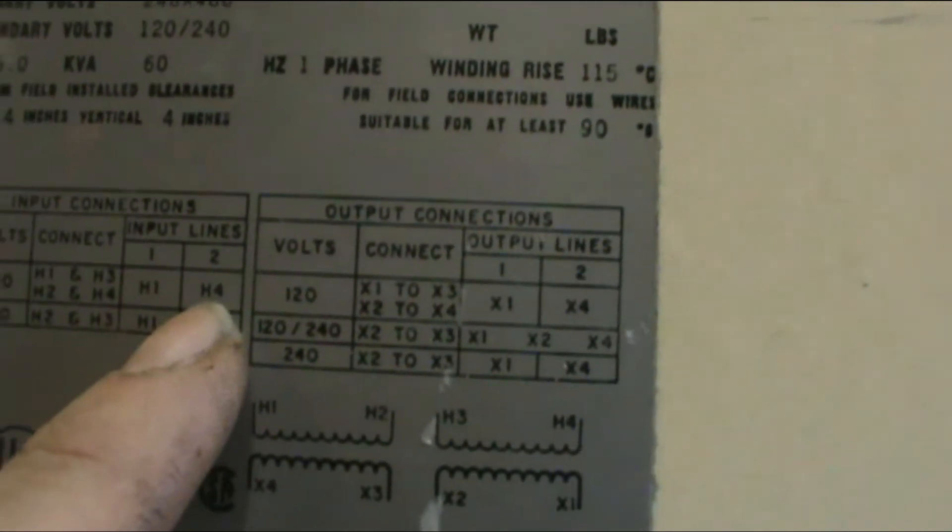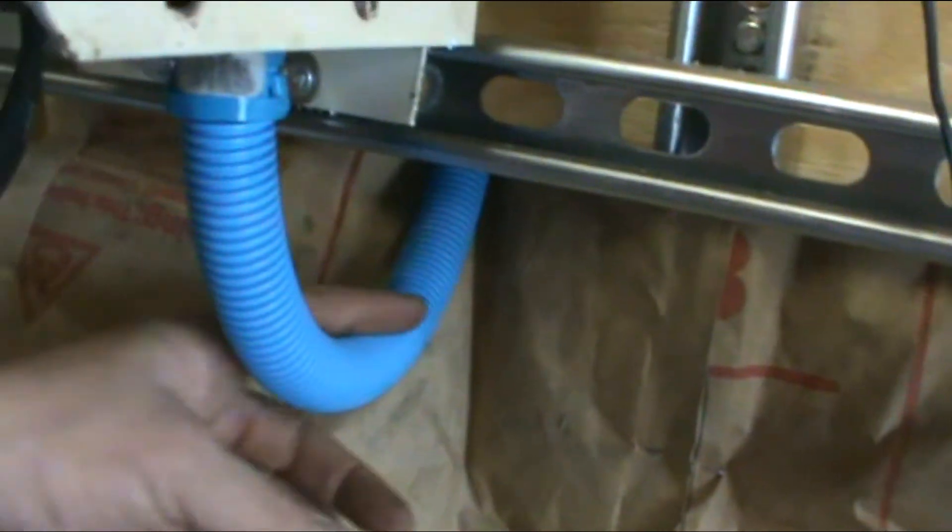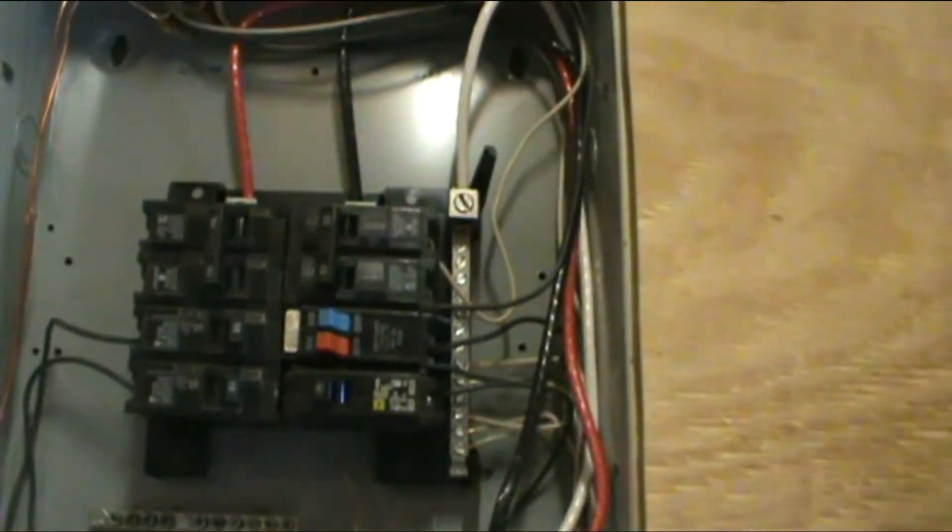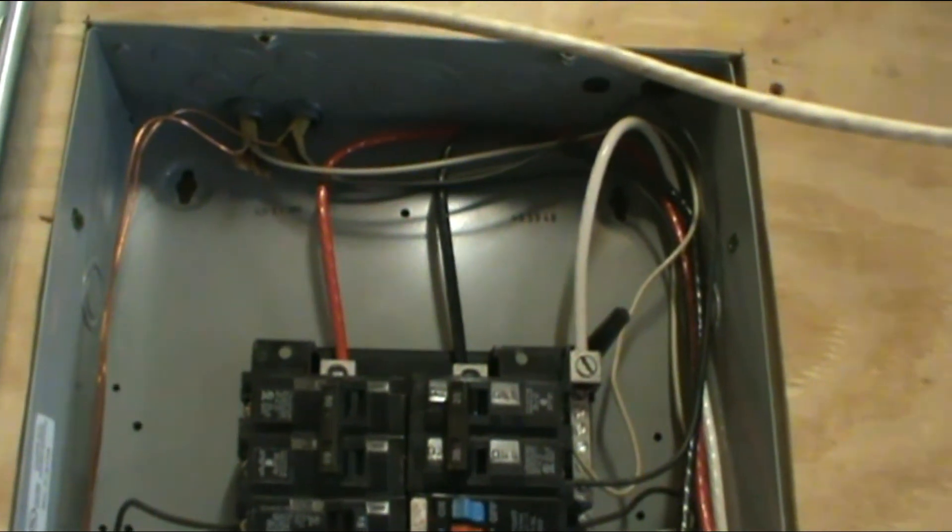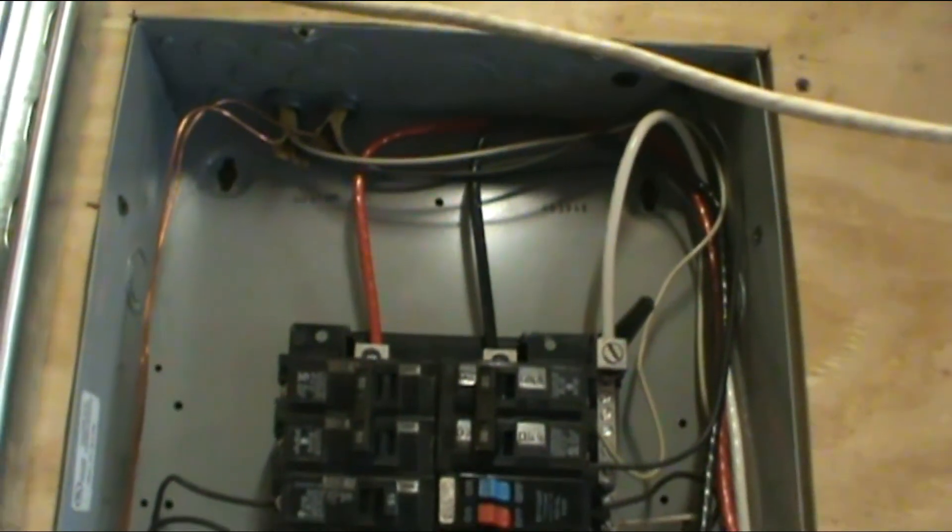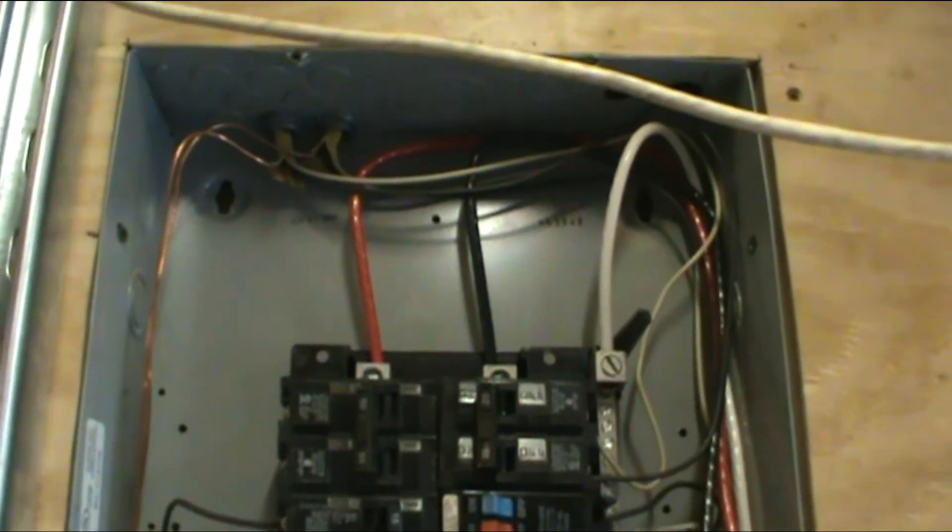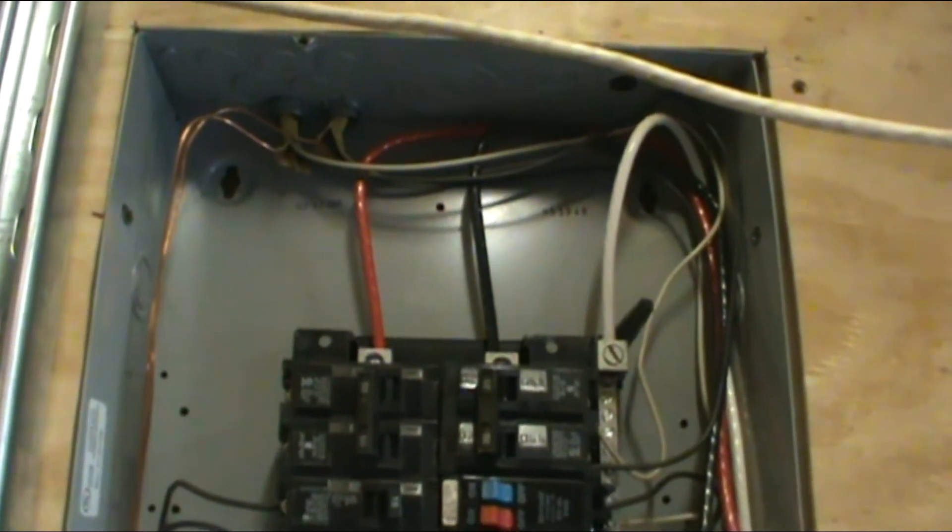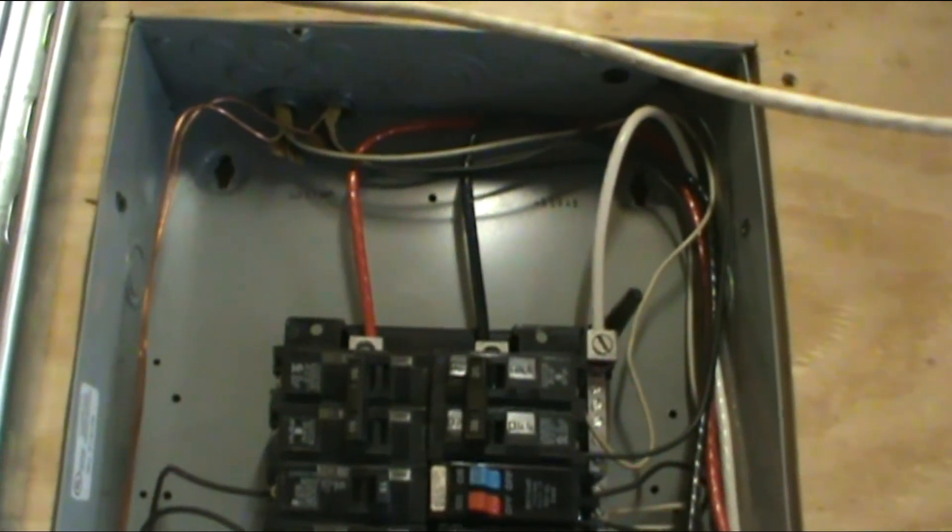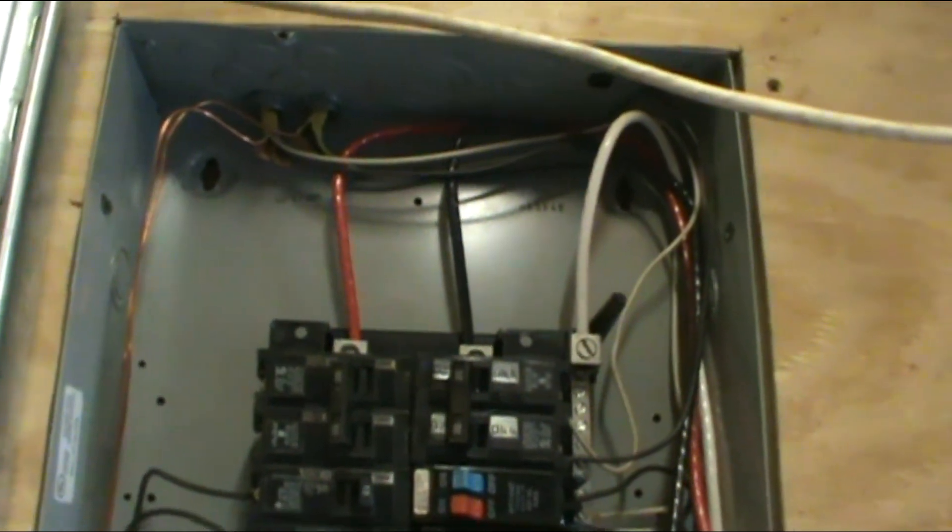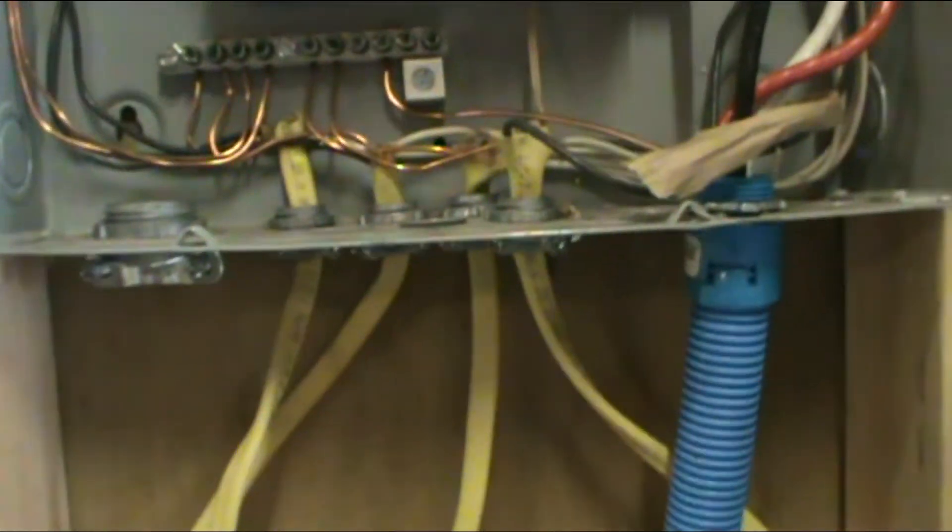I have H1 and H3 wired together, H2 and H4 wired together, and you bring your taps off of H1 and H4. Those lines are connected to the wire coming out of that breaker box. It goes inside of here, then through another piece of conduit behind everything into the master box here for the PIP. I've got a 50 amp breaker up there, that's going to run a circuit from here into my house. I'm gonna put a small breaker box in there for lighting and maybe the fridge and deep freeze.